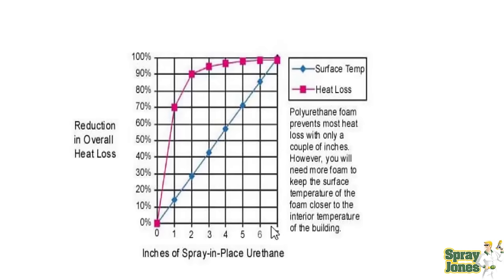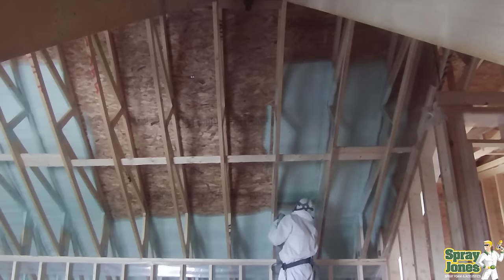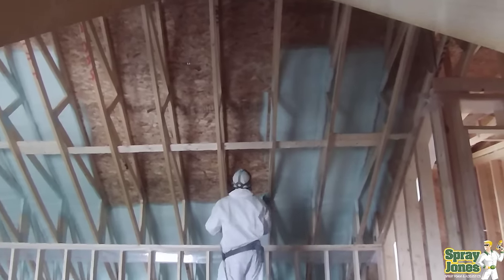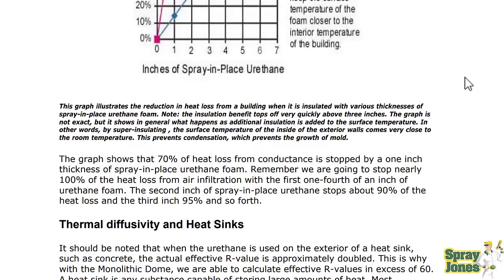People who say you need 6 or 7 inches of foam are adding massive cost — this is where the system is rigged. If we're just going to hit a prescriptive white-paper number requiring 5, 6, 7, or 8 inches of closed-cell or open-cell foam, we're past the point where heat loss actually flattens out. The graph shows that 70% of heat loss from conductance is stopped by just 1 inch of spray-in-place urethane foam. Nearly 100% of heat loss from air infiltration is stopped with the first one-quarter inch. The second inch stops 90% of heat loss, and the third inch reaches 95% — only a 5% gain from 2 to 3 inches.